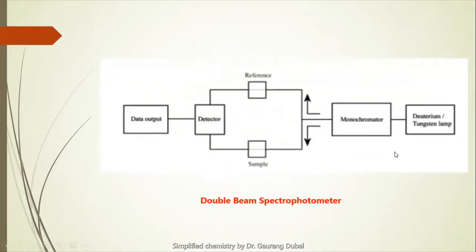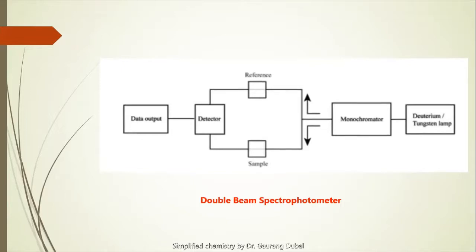You can see the source here — it goes to the monochromator and is split into two paths: one reference and one sample. So here the light is not going directly to the sample but first gets split and goes to two parts.